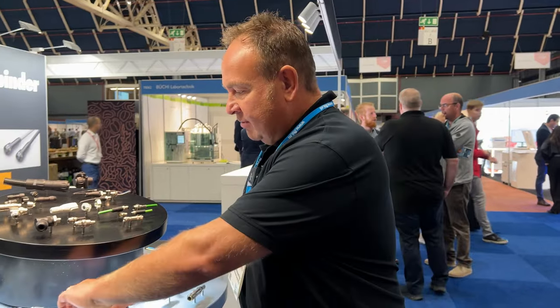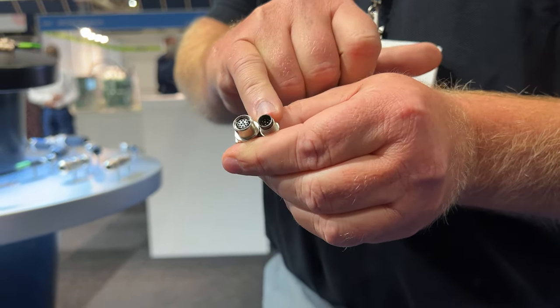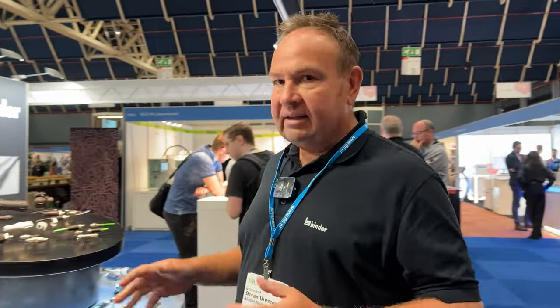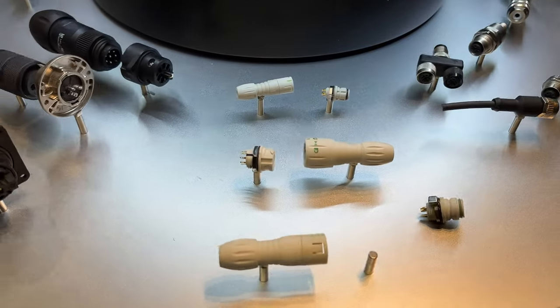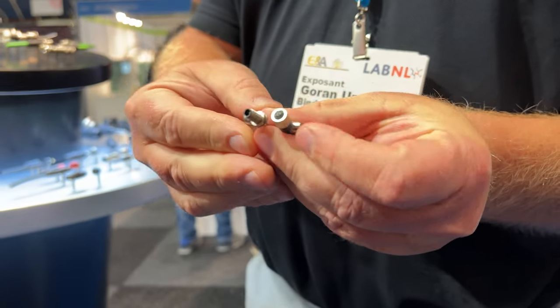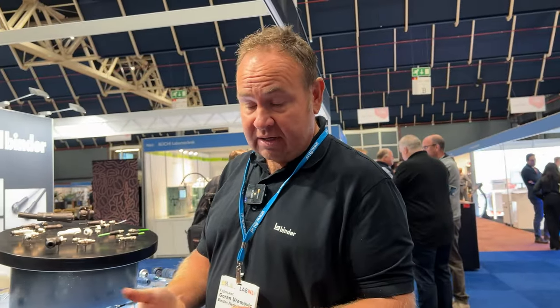Going smaller: the M8 was originally made as a 3 or 4-pin connector, but we now offer M8 connectors with up to 12 pins — Binder pioneered this. We developed this connector and it became an industry norm, meaning competitors producing this size must follow our pin arrangement standard. Twenty years ago when I started at Binder, we also developed the M5 connector — a 5mm fixing thread connector with four pins, each rated at 1 amp.